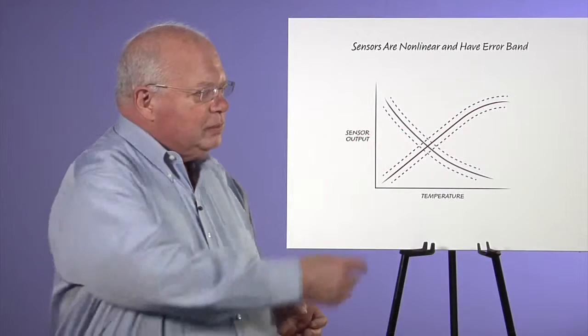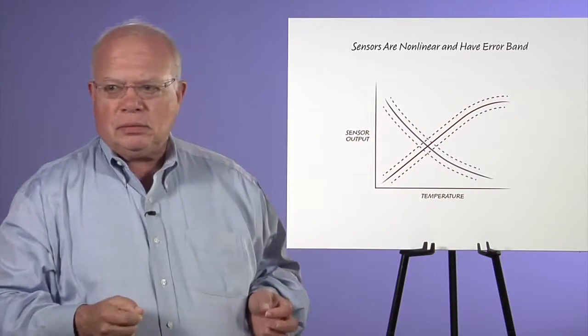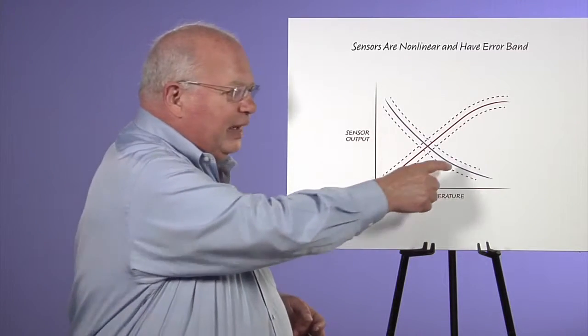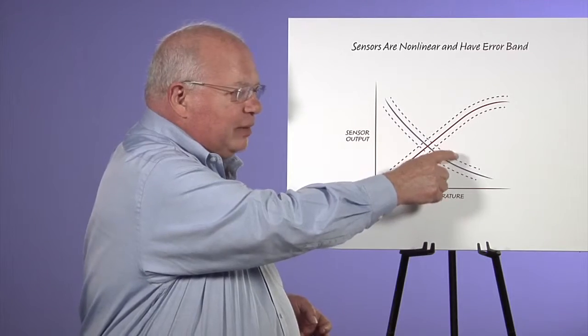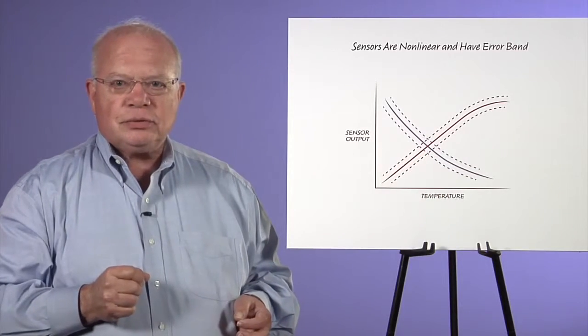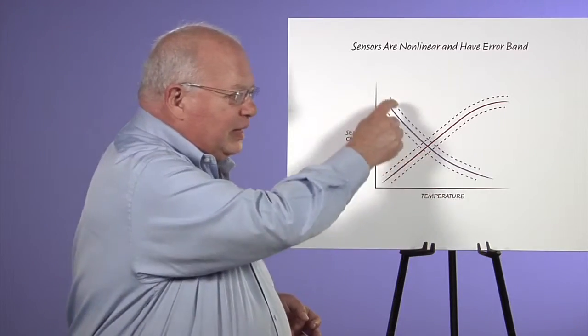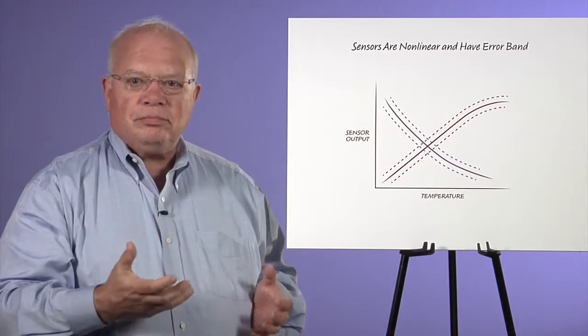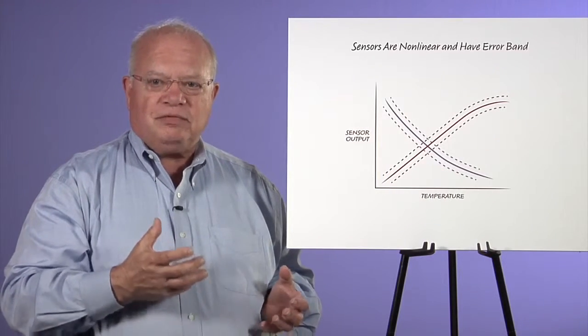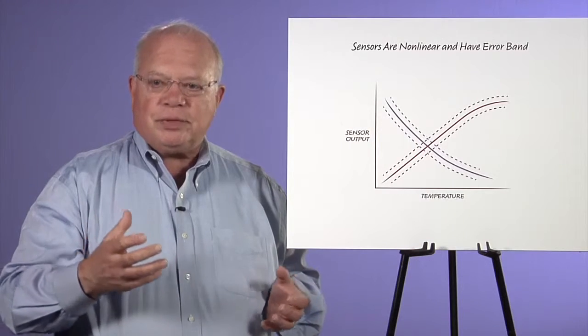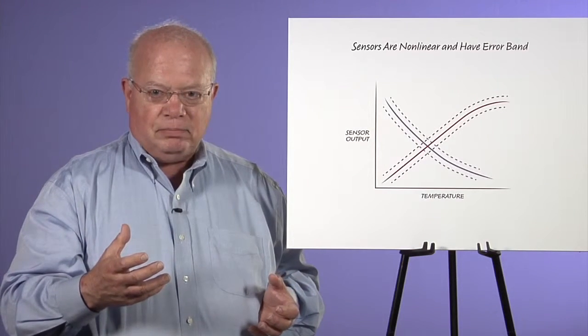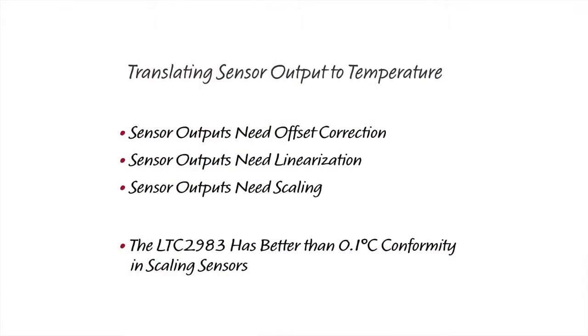temperature. The sensors are not linear. They have offset. If this is the perfect sensor, they can be anywhere in a range. They need a scale factor because their output in terms of millivolts or microvolts per degree C is not always the same. So we have to provide offset correction, scale factor correction, and linearity correction. And that's all done in a digital processor in the 2983.